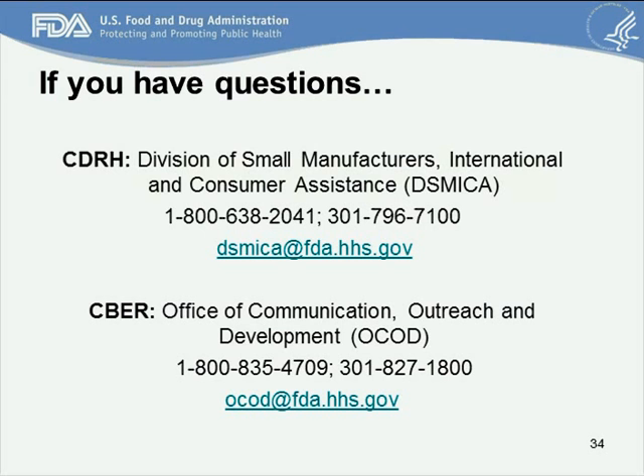Yes, so the Q-submission program and the pre-submissions apply for all different types of FDA submissions, IDEs, PMAs, HDEs, 510(k)s, and all submissions, whether they're going to OIR or ODE, should come in through the Document Control Center. Thank you. You're welcome.